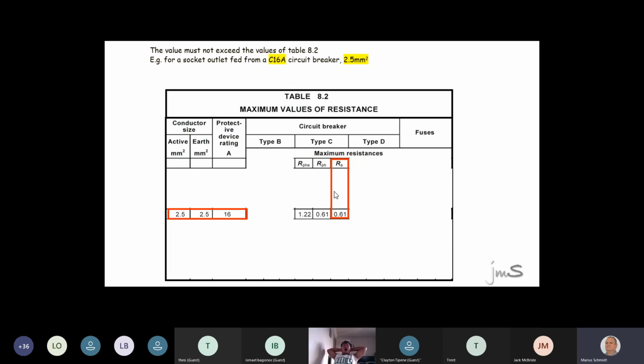Great stuff. Right, guys, you all agree that from here to the plug might be 10 or 15 or 20 meters. Your multimeter leads are only 2 meters long. So if I go to the switchboard and I short out phase and earth, and I go back to the plug, you all agree I measure earth and phase back. So if the one is 0.61 and the other one is 0.61, if you add that up, it gives you 1.22. So what this thing did, it's actually thinking for you.